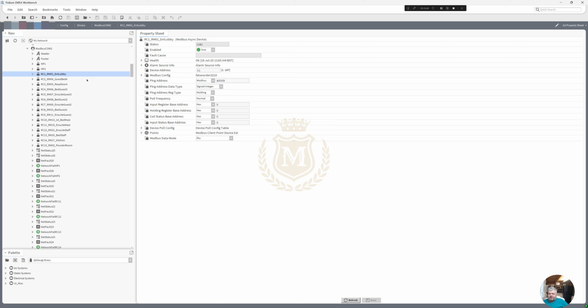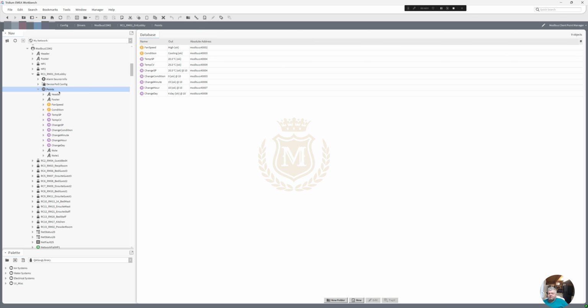And a normal room controller, if we go to a room controller here, points, fan speed, condition, so they can select whether they want heating or cooling. They can select the fan speed, and they can select the set point. The control variable, actually off that room controller, which we are not using. We're using a temperature sensor that's in the room, the set point, and then we've got the time of day that we send to them with the clock, so that the station's clock we send to them via Modbus, the hour, the day, the minute, so the clocks always give the right time.